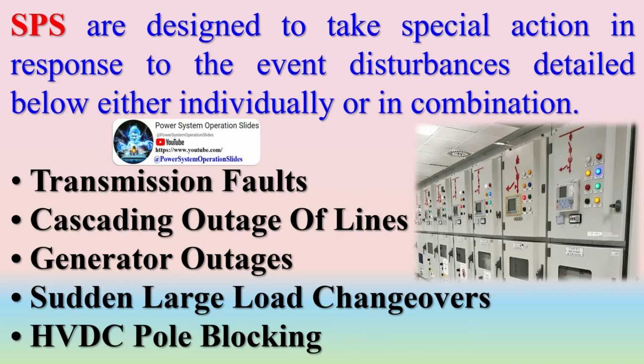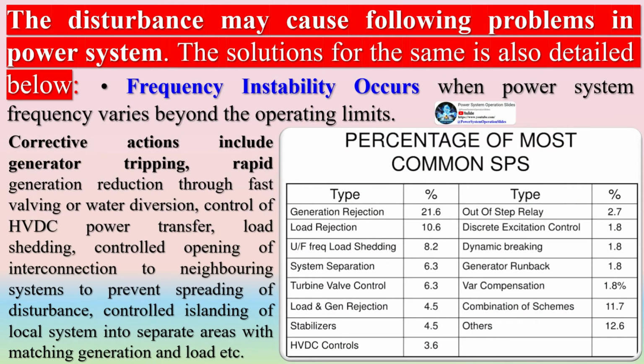The design of SPS should be properly coordinated with the existing protection system for maximum reliability. SPS are dynamic security control systems and are designed to control power system stability in cases where the uncontrolled response is likely to be more damaging than the controlled response. SPS are devised by offline analysis as opposed to online real-time control. The reason behind this is that power system response is too fast to allow sequential control system logic. Involvement of a grid operator's human intervention for corrective action should be kept to a minimum compared to SCADA EMS.